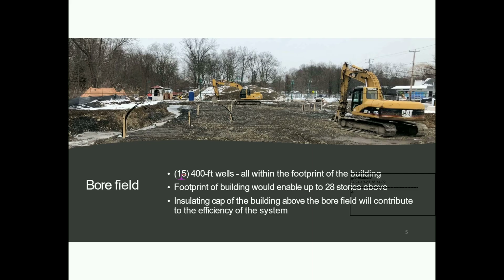We put 15 boreholes all underneath the building, and they are only 400 feet deep, because if we have the room, we like to make them 400 feet deep. It causes the best balance between pressure drop, pumping power, etc. And you heard that one of the arts here is to pump the entire building with an average of 400 watts. This is a lot like a residential circulator, which does it for this entire 60,000 square foot building. But the art is to engineer it so this is enough, and it's enough for all the heat pumps at all times.